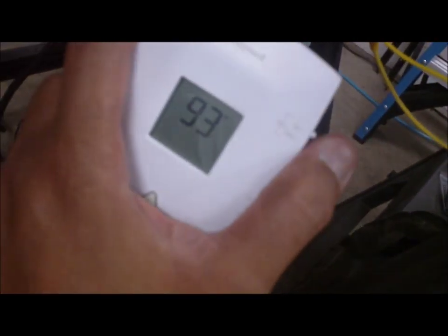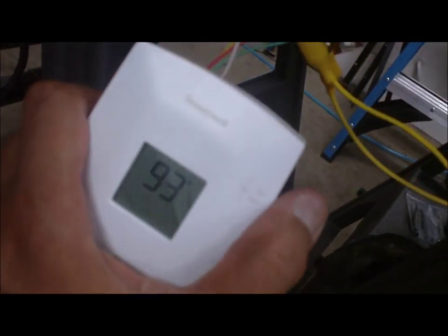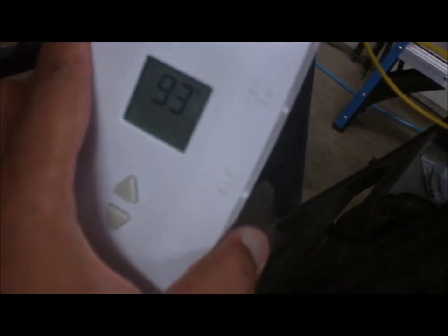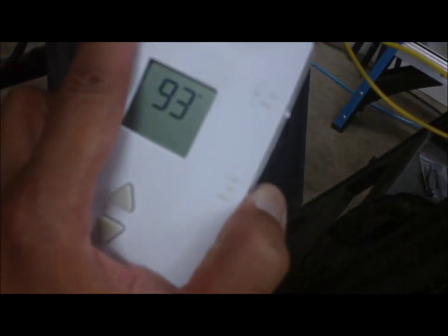I'm going to turn it off, put it on auto. That will shut it off. And now we're going to call for cool, and just watch the contact pull down as soon as I turn it on. There it is. Now it's energized. This relay right here, this one I'm pointing at, not touching it, it's live.